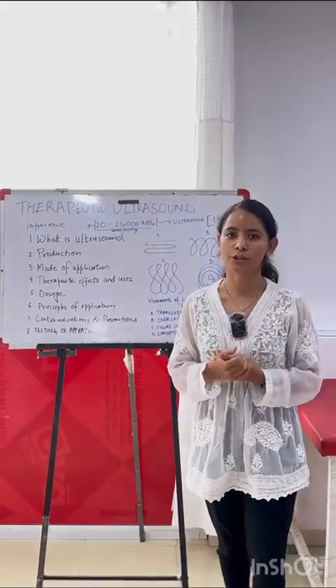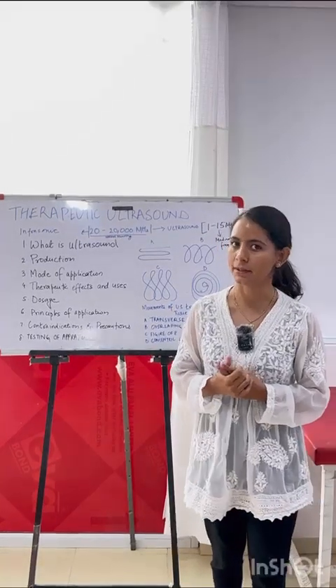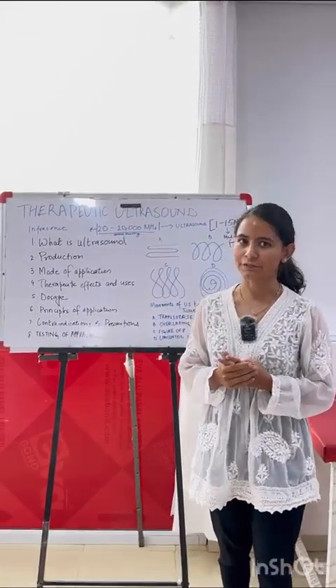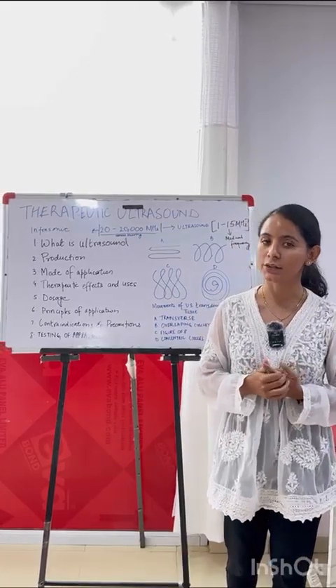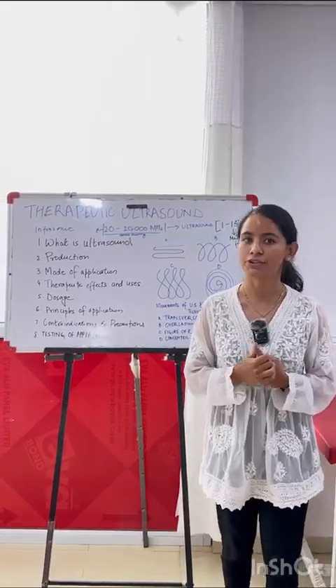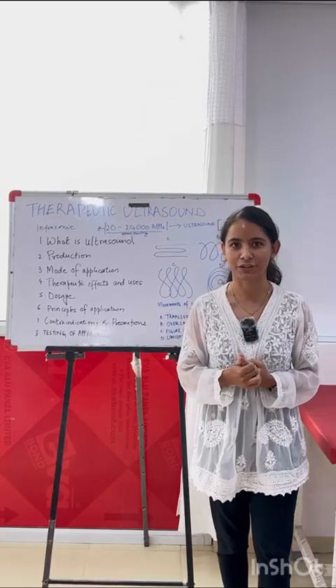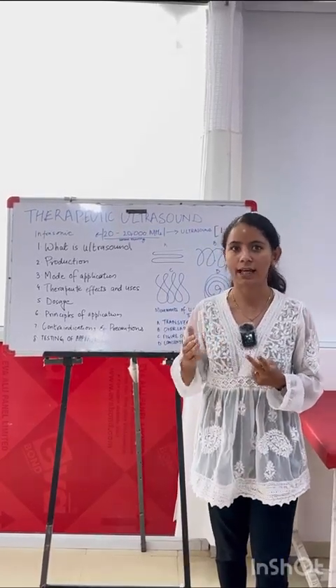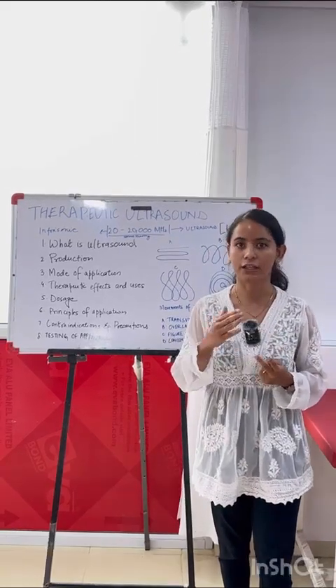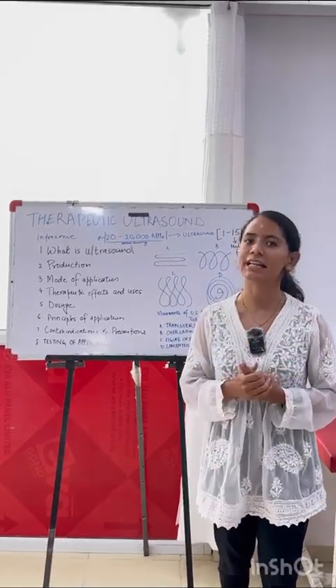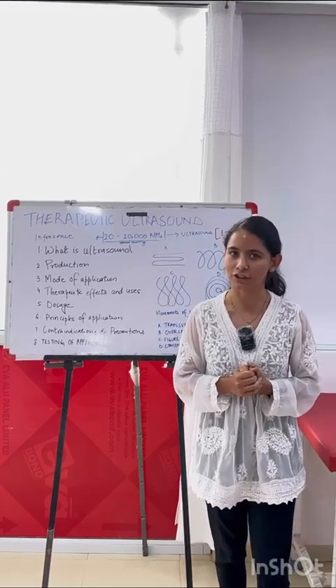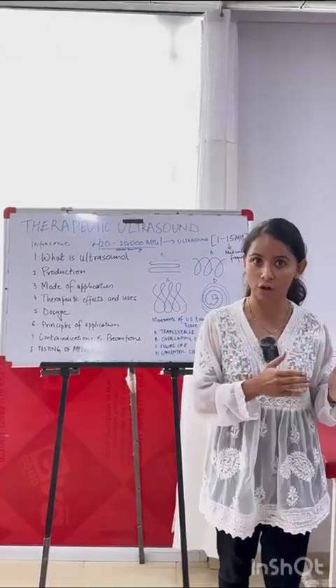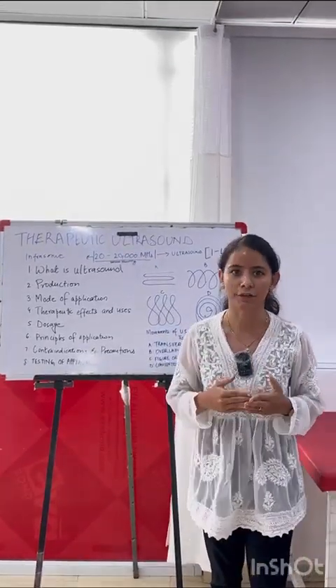Mode of application. There are two modes of application: continuous and pulse. For heating effect, we use continuous mode, and for healing effect, we use pulse mode. In continuous mode, the ultrasound is on throughout the treatment session. In pulse mode, it comes in a pulse on and pulse off ratio. This on and off ratio throughout the treatment is known as the mark to space ratio, and the duration when the ultrasound is on is known as the duty cycle.